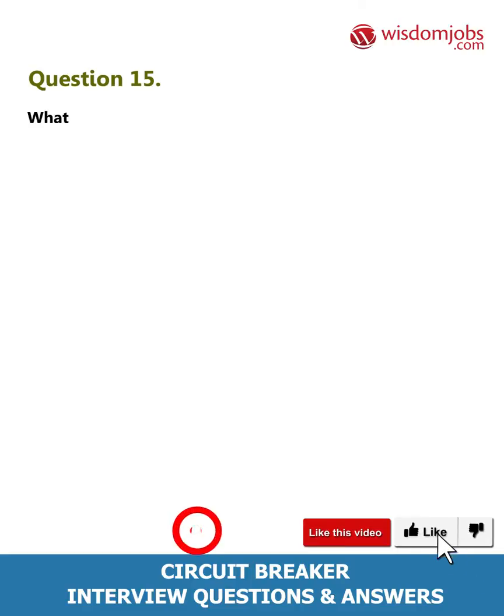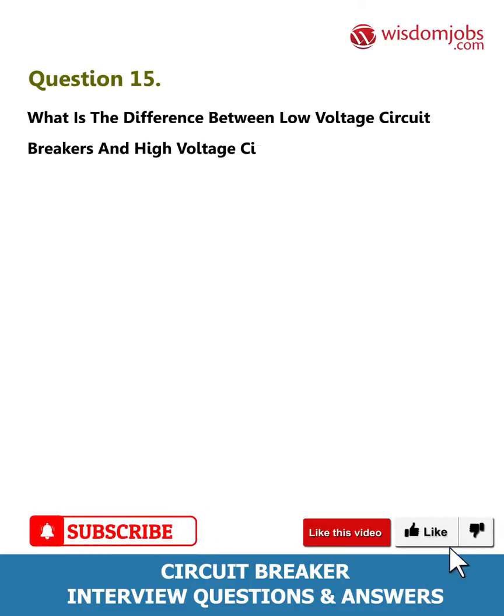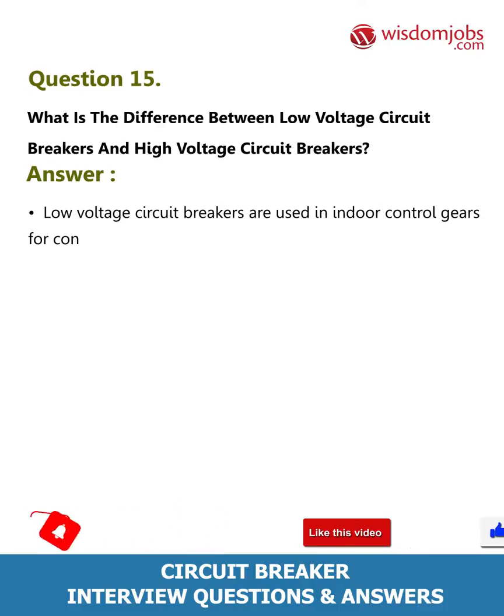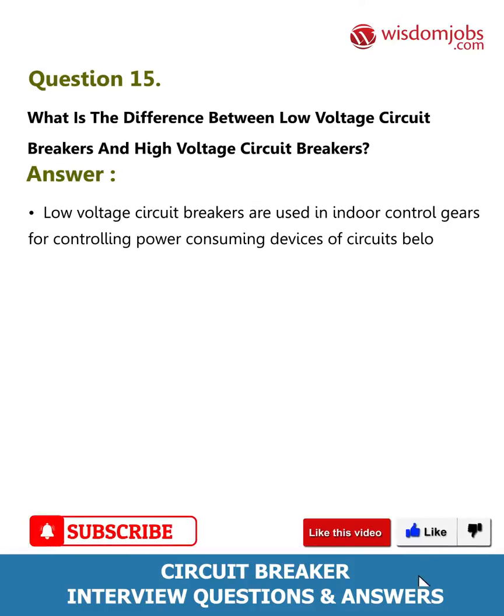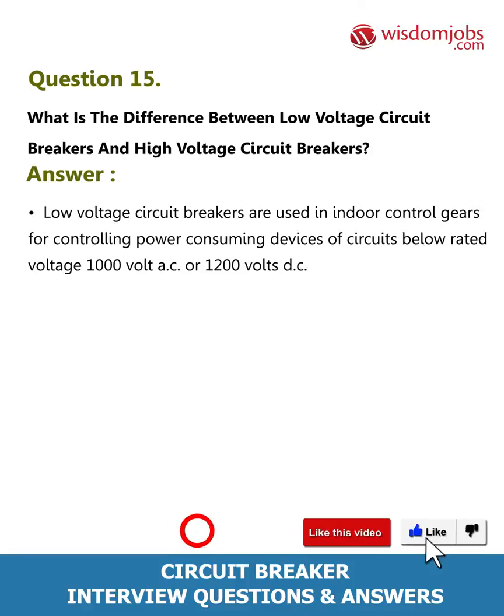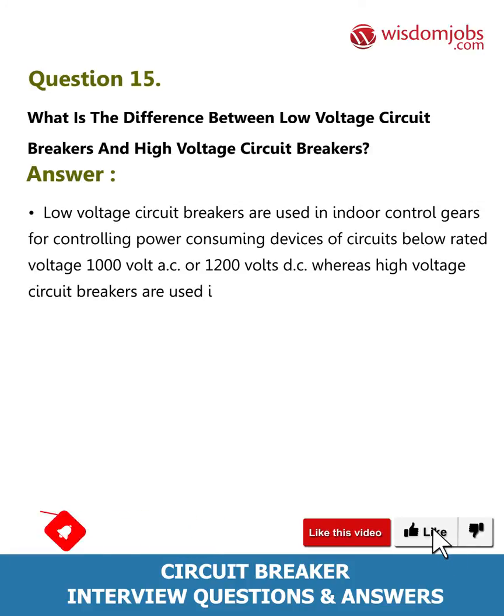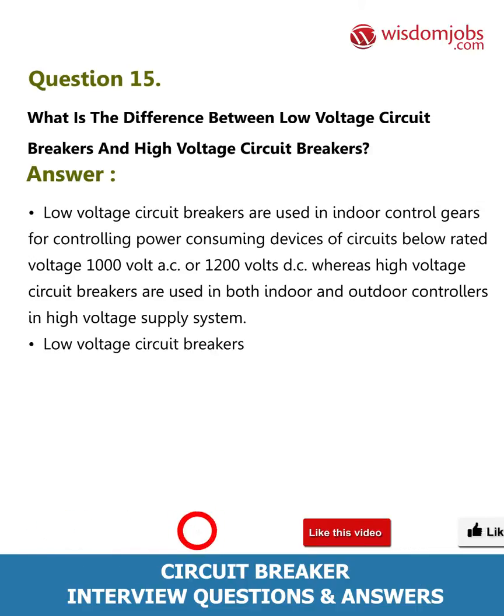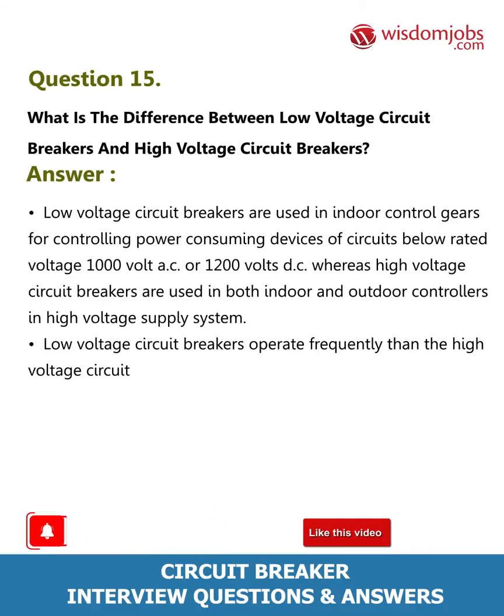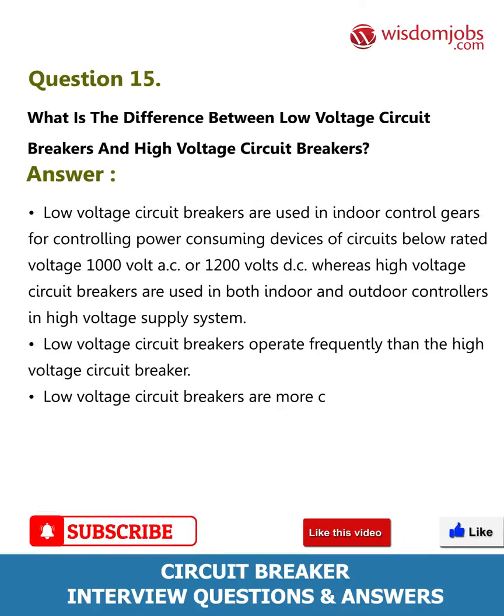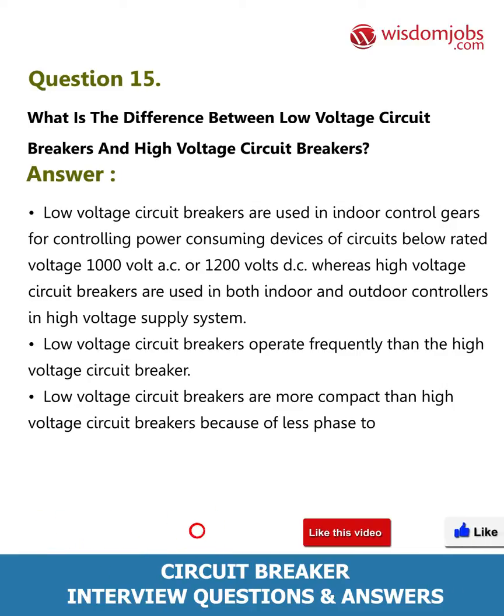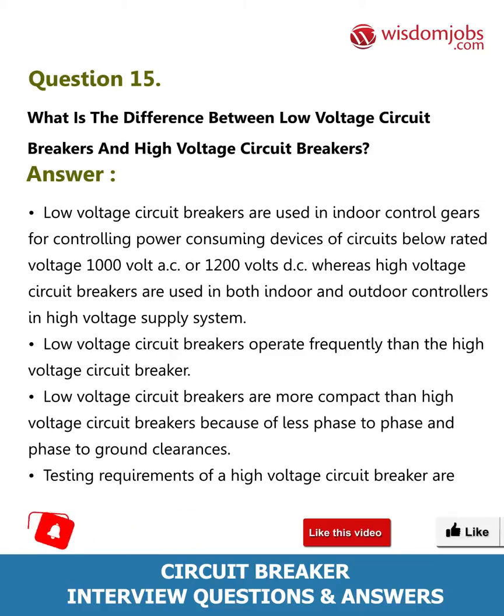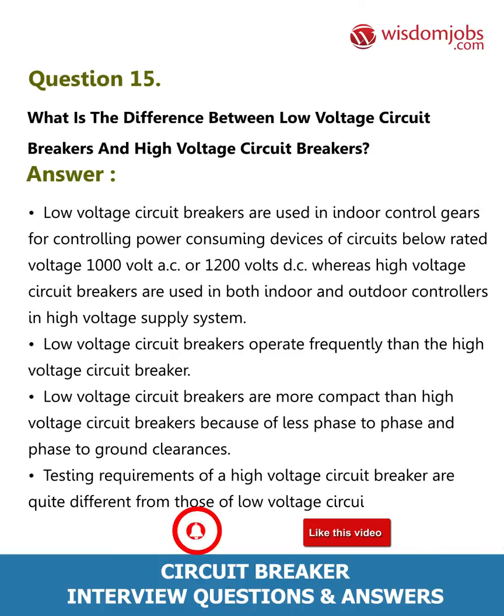Question 15: What is the difference between low voltage circuit breakers and high voltage circuit breakers? Answer: Low voltage circuit breakers are used in indoor control gears for controlling power consuming devices in circuits below rated voltage 1000V AC or 1200V DC, whereas high voltage circuit breakers are used in both indoor and outdoor installations in high voltage supply systems. Low voltage circuit breakers operate more frequently than high voltage circuit breakers, are more compact due to less phase-to-phase and phase-to-ground clearances, and have different testing requirements.